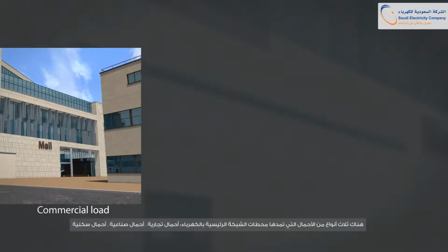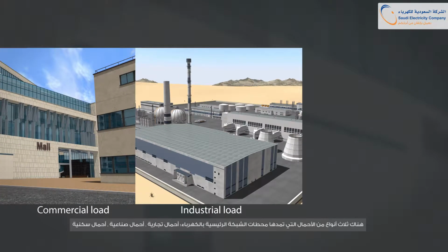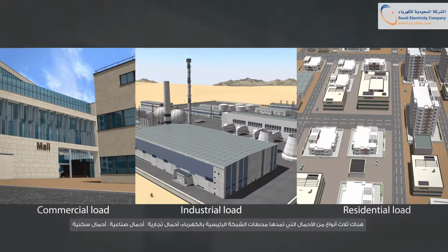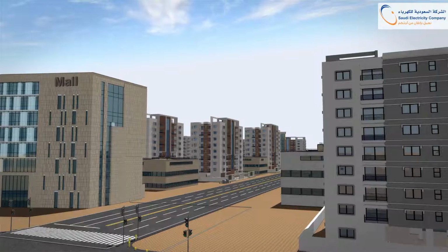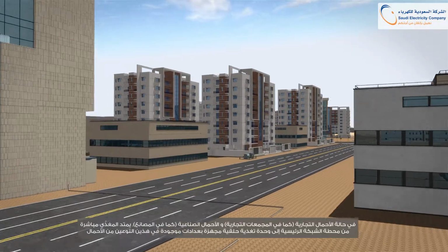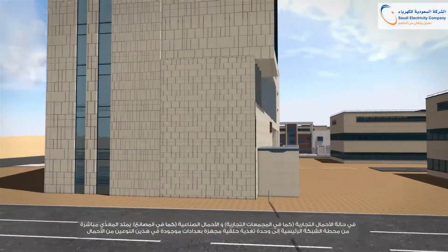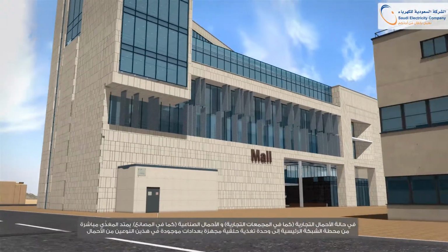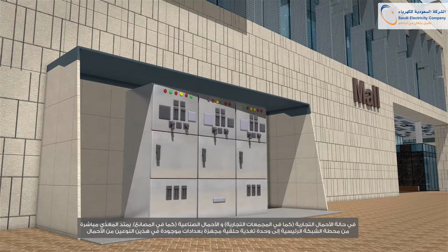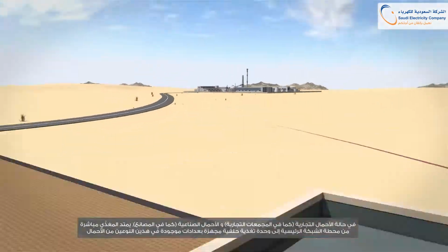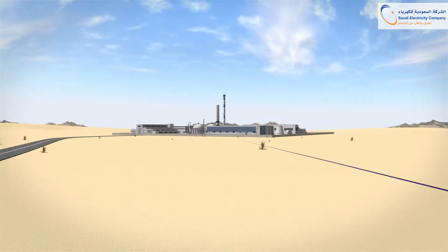There are three types of loads that can be supplied with power by grid stations: commercial load, industrial load, and residential load. In the case of the commercial load, such as a mall, and the industrial load, such as a factory, a feeder goes from the grid station directly to a metered ring main unit located in each of the two load types.